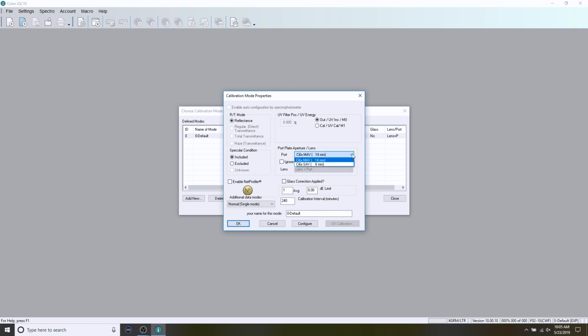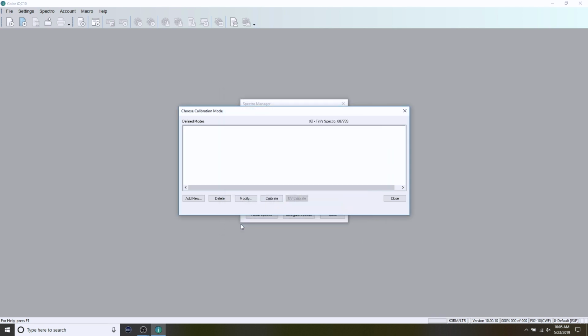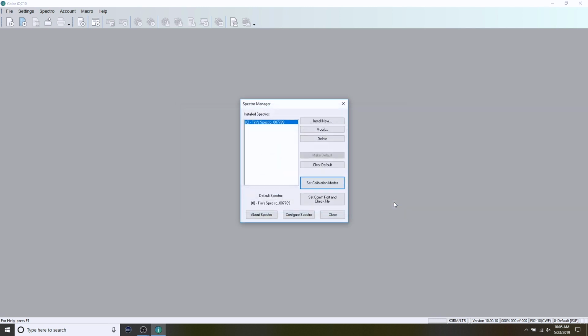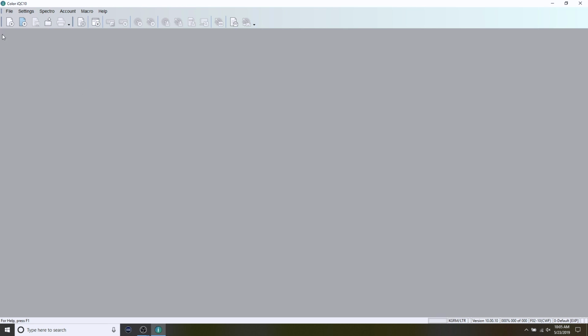I can choose on this instrument which port I'm using because it's switchable between a 14 and a 6mm aperture. I can choose whether or not to calibrate the UV energy. I can choose the calibration interval. By default, it's 240 minutes or 4 hours. So we're going to leave it there in its default state, and we could click on the word calibrate here if we wanted to calibrate at this point. I'm going to not do it that way and show you how I might do it in more normal use.